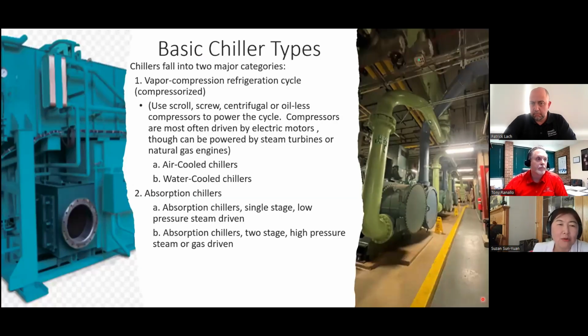Let us do a quick fundamental overview of the chillers. There are mainly two types of the chillers: vapor compression refrigerant cycle and vapor absorption refrigerant cycle. On your right is a centrifugal chiller. A single effect absorption chiller is on your left, which uses the lithium bromide and water solution. It uses hot water as a heating source. Next slide, please.